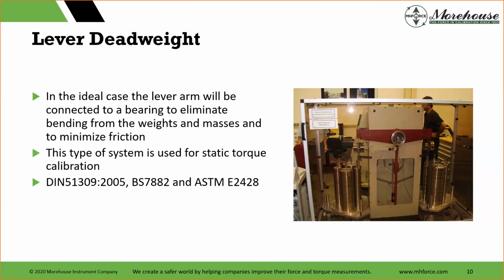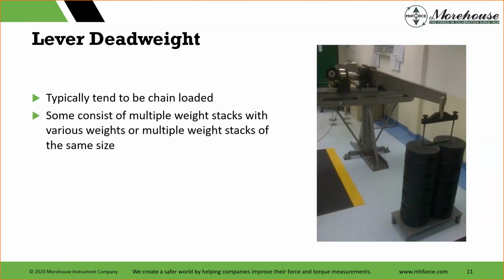They were able to say, hey, I'm claiming way too low uncertainties here, or hey, I have some friction problems, maybe I should support my arm. Really just interesting things. So again, with the lever dead weight, these typically tend to be chain loading, which means you pick up one weight and then you have to pick up another weight. Some consist of multiple weight stacks, or multiple weight stacks of the same size.